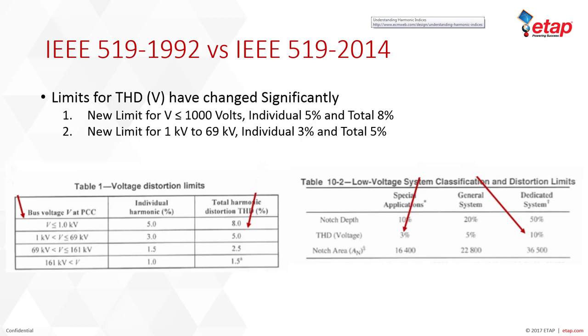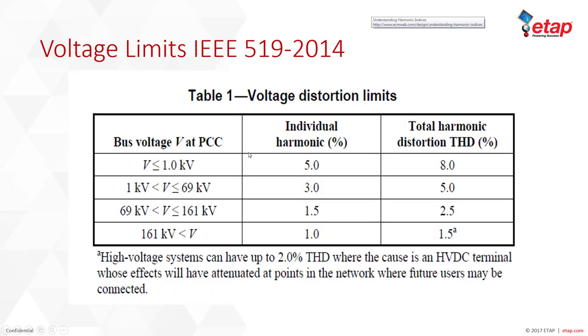So for buses under 1 kV, you now have an increased allowable total harmonic distortion voltage, which increased from 5% to 8%. This has been built into the new version of ETAP, so you'll have a harmonics rulebook containing these new voltage limits. You can apply them not just at the point of common coupling, but with different global settings or specifically at individual locations.